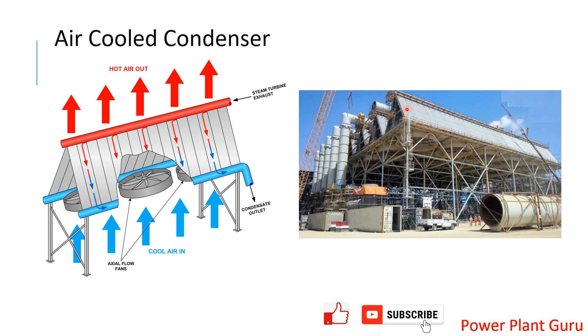The fins are not visible in this image but will be shown in the next slide. There are spaces between the tubes through which air passes out, enabling heat exchange between the steam and the ambient air. These fans are VFD-controlled so you can increase or decrease the quantity of air passing through according to the turbine load. There is no water used as in a conventional cooling tower, which reduces water consumption. Capacity-wise, in colder places this type of condenser can give the required output.